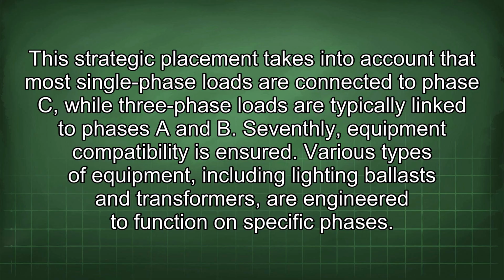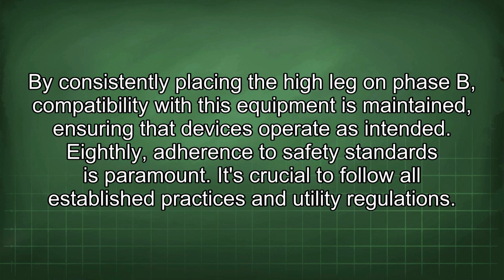Seventhly, equipment compatibility is ensured. Various types of equipment, including lighting ballasts and transformers, are engineered to function on specific phases. By consistently placing the high leg on phase B, compatibility with this equipment is maintained, ensuring that devices operate as intended. Eighthly, adherence to safety standards is paramount.